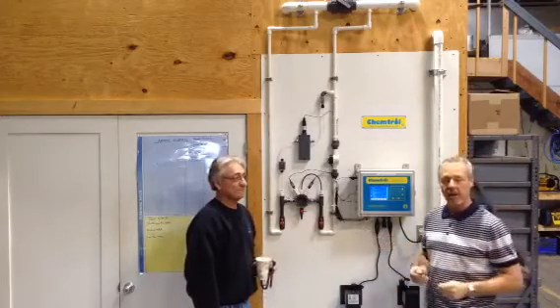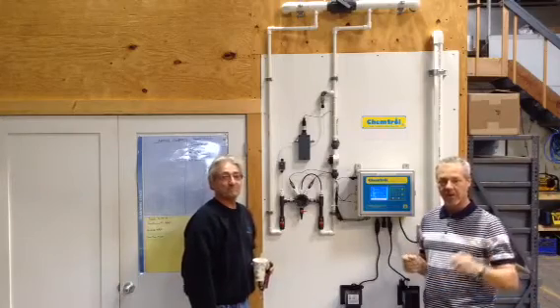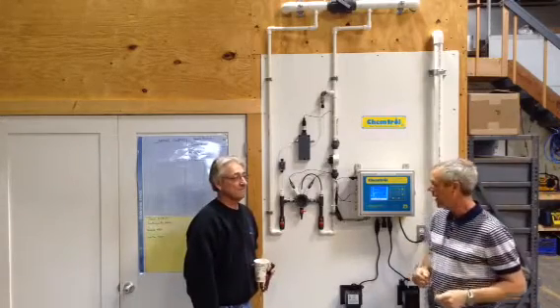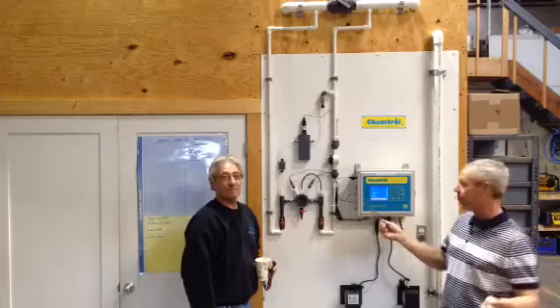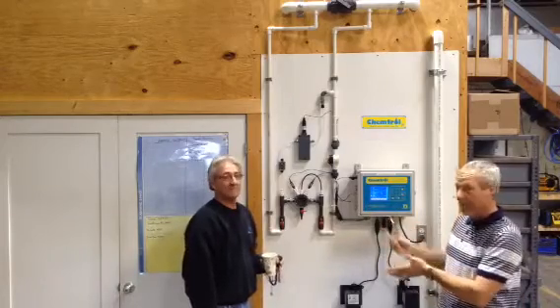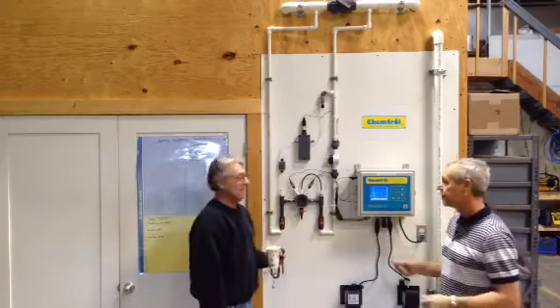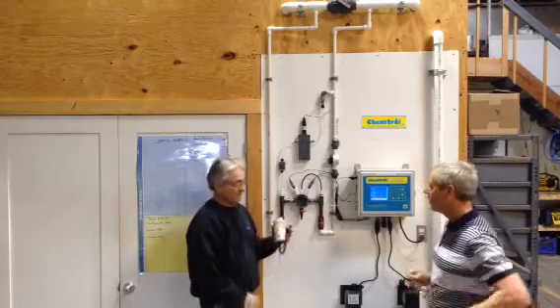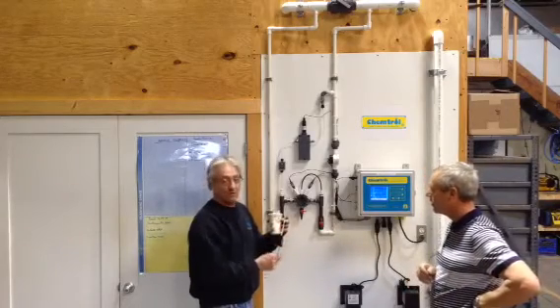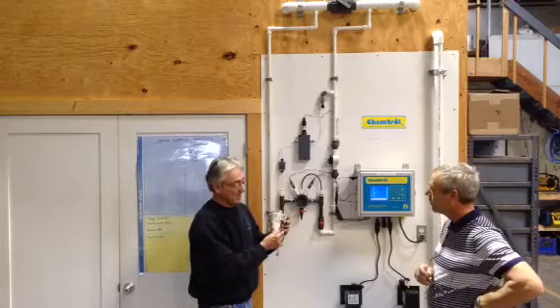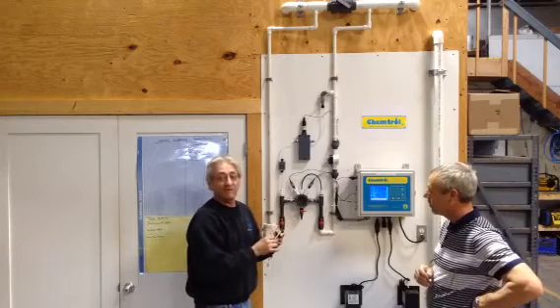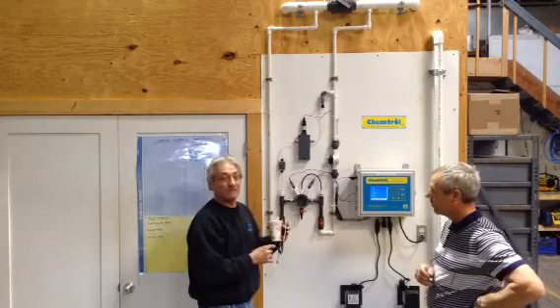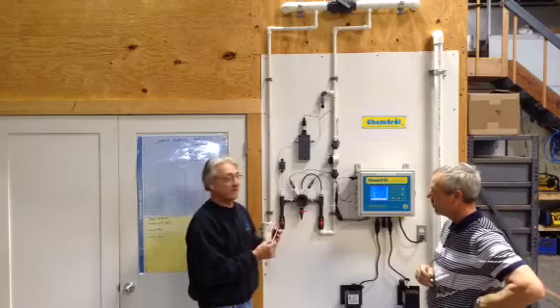Maintenance is this month, and we've got a lot of great stuff on there. Funny article from Glenn, and Andy's going to talk a little bit about why we do a small bit of maintenance to our probes. Any of the controllers that are out there all have the part per million, chlorine, and ORP probes. They collect oil. When the oil gets on it, they get dirty. They don't pick up the right signals. So you're going to have to clean them periodically.